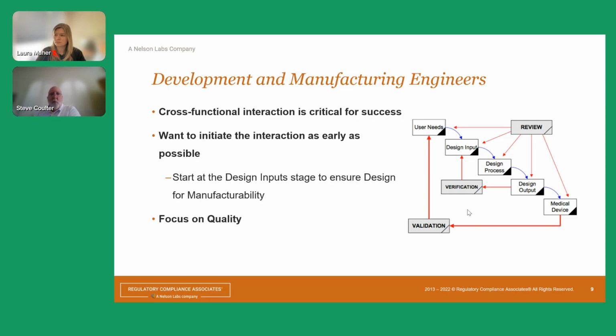So now, one of the things that's critically important, in my opinion, is going to be early cross-functional interaction. The diagram over here on the side is the famous waterfall model out of the FDA guidance documents. And it lays out several things. The white boxes in the middle here are your design process. We're going to come back to this in a second.